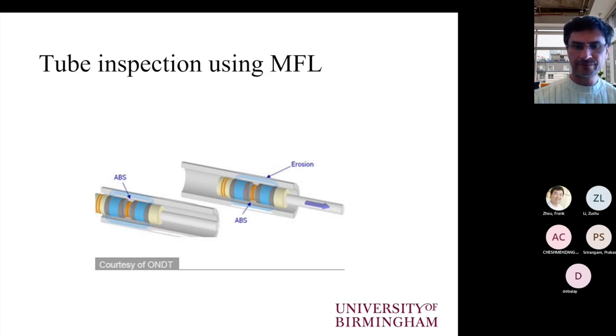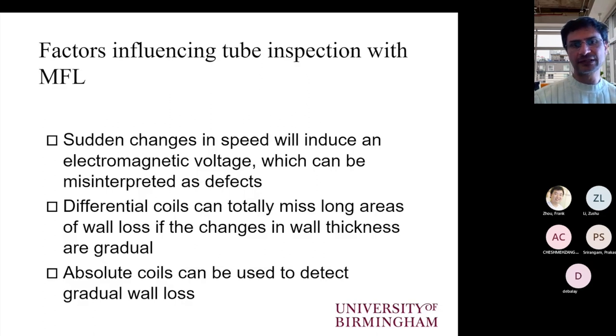The factors that can influence inspection with magnetic flux leakage include sudden changes in speed, which can yield data that appear to be real defects. But of course, if we are doing the inspection, we can realize when we have done this, especially if we have enough experience. The differential coils are not designed to pick up general corrosion, because their values will eventually go back to zero when we are subtracting each other.